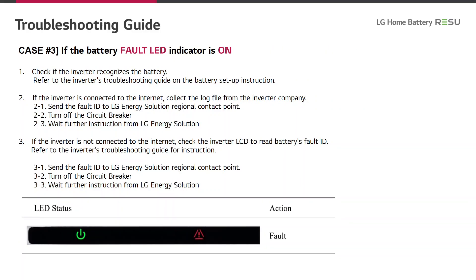Case number 3: the battery shows a fault LED and the indicator is on. Check if the inverter recognizes the battery, and refer to the inverter's troubleshooting guide on battery setup instructions. If the inverter is connected to the internet, collect the log file from the inverter company, send the fault ID to LG Energy Solution regional contact point, turn off the circuit breaker, and wait for further instruction from LG Energy Solution. If the inverter is not connected to the internet, check the inverter LCD to read the battery's fault ID, refer to the inverter's troubleshooting guide, send the fault ID to LG Energy Solution regional contact point, turn off the circuit breaker, and wait for further instruction.